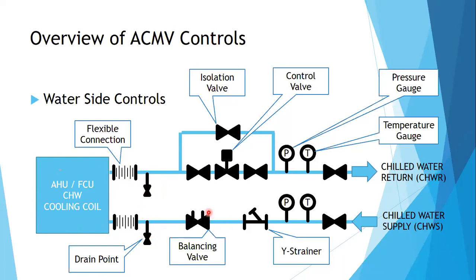Okay. Balancing valve. Balancing valve is a flow restrictor, similar to a control valve. What's the difference between the balancing valve and the control valve? The balancing valve limits the amount of water permanently that can pass through. So when the water goes here, there's always a fixed amount, a measured, preset amount of water that can pass through. The rest is being held or stopped.